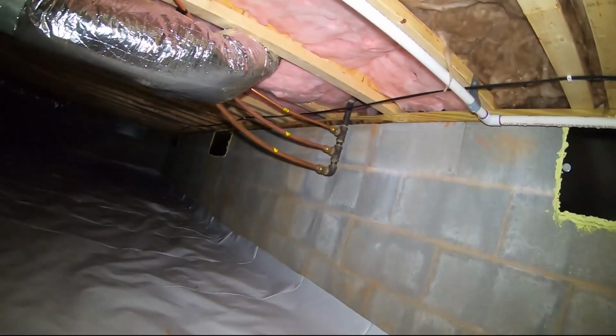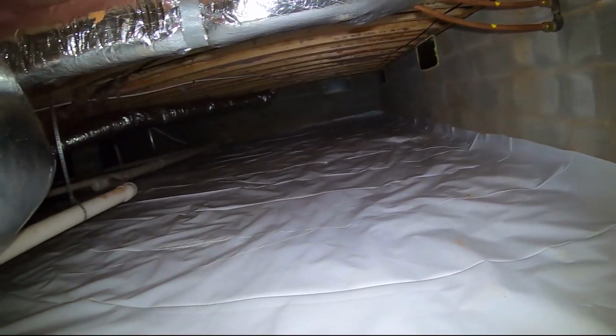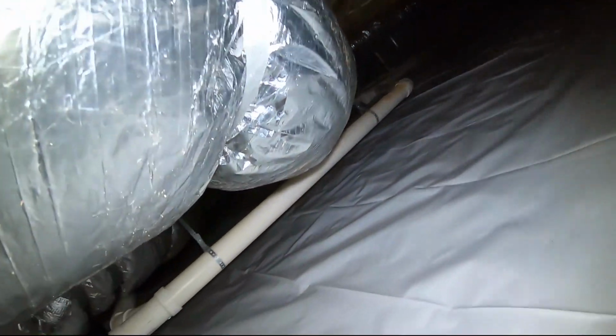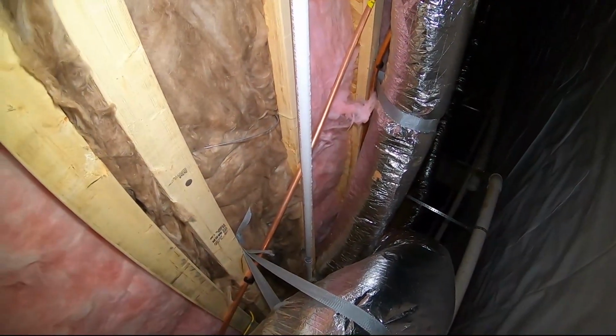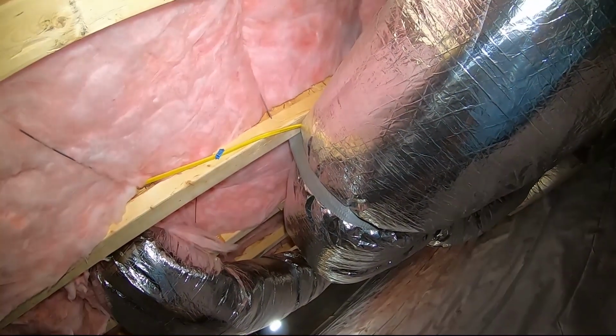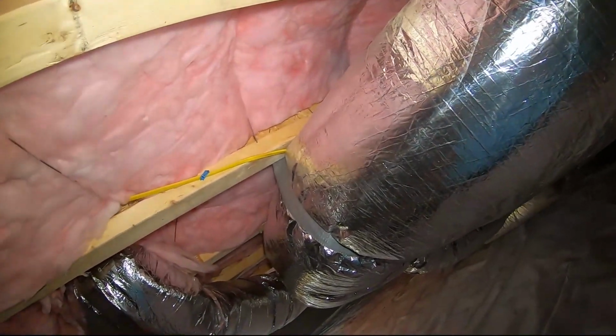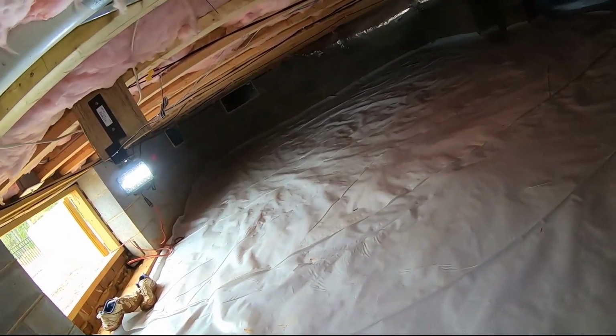Of course, it's a new house, so everything is new, but the smell is so much better in here since we were able to get the moisture problem under control. On the initial visit, all these ducts were dripping condensation, and of course, this homeowner was very frustrated with that, trying to get this under control. And the dehumidifier is working overdrive at the moment to get things dry. But once we equalize, as soon as a month from now, we could start getting good fall weather and be able to take advantage of the outside air.